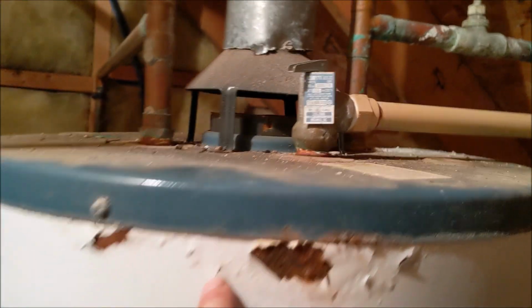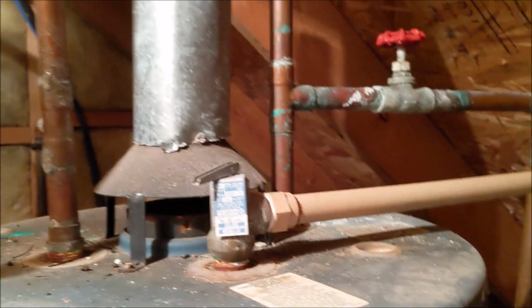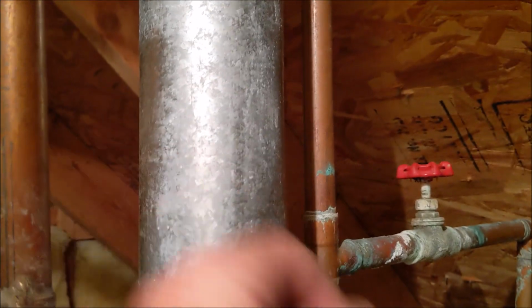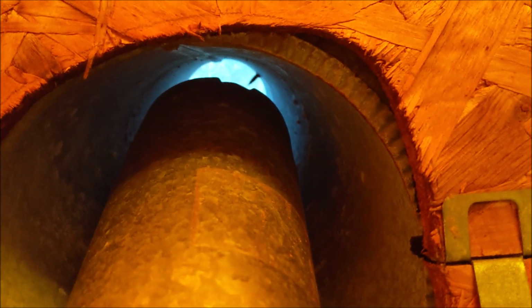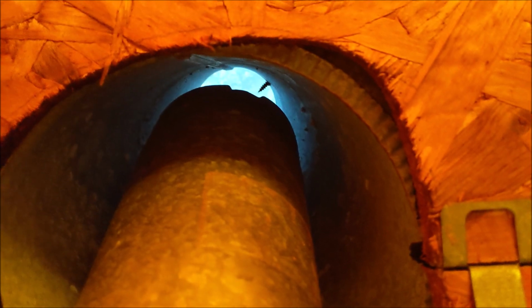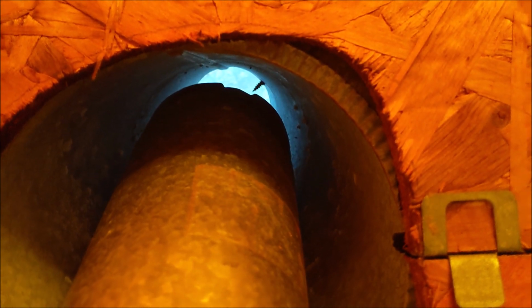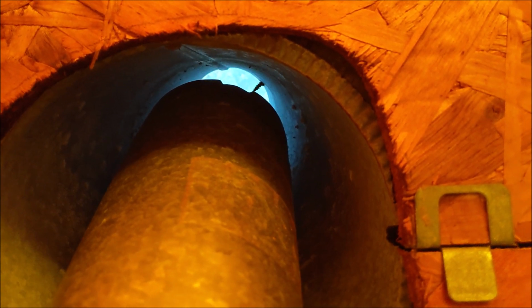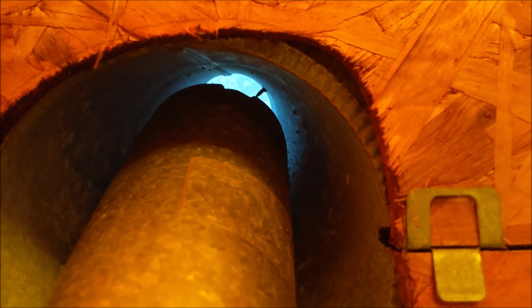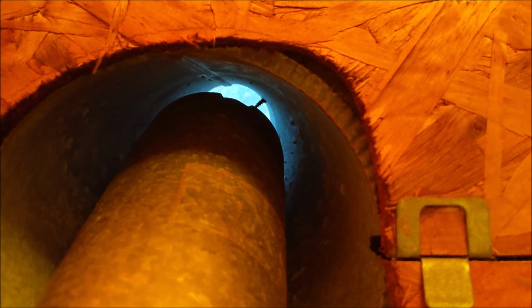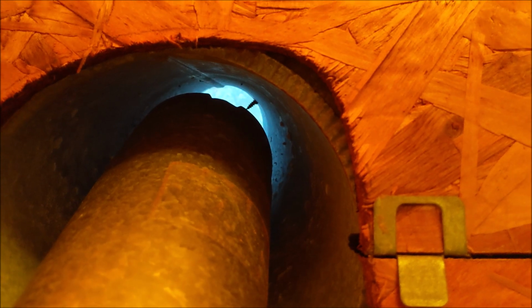We've got some typical rust here, typical rust there. We had it at the other water heater. This is a single wall pipe. Basically, it's just one piece of sheet metal. They strapped it, and as you'll notice, it doesn't go all the way out the jack. So when you go outside and look at the roof and the jack, it doesn't extend out past the roof jack. So basically, the draft gets blown back in, and the hot air and condensation get thrown back around, and that's what causes the rust on the jack. The older water heaters didn't have to do it. Today, all of them have to go out.